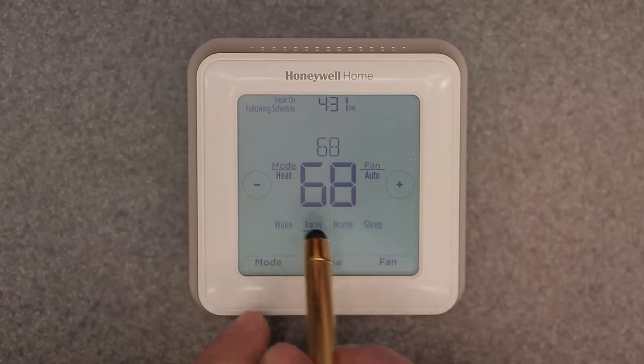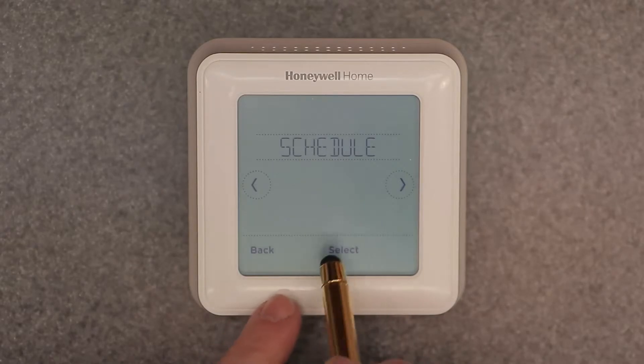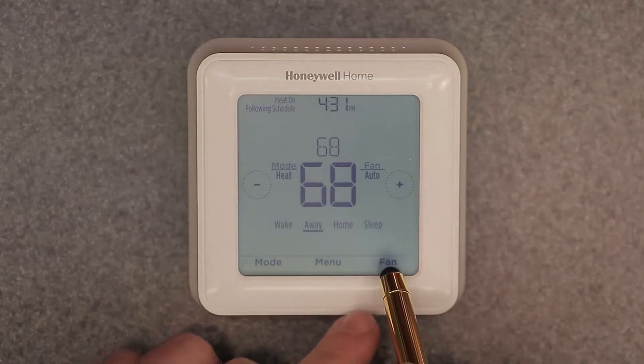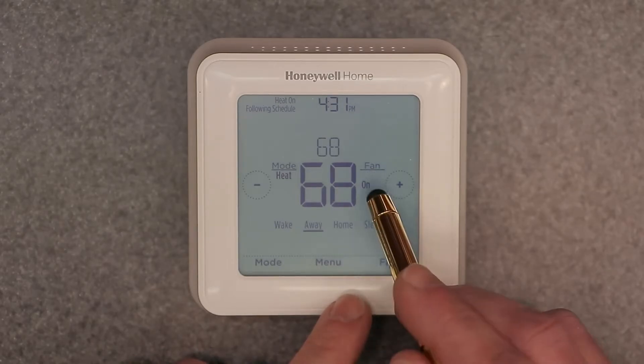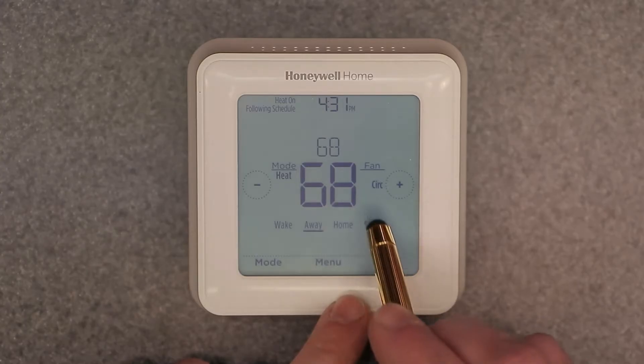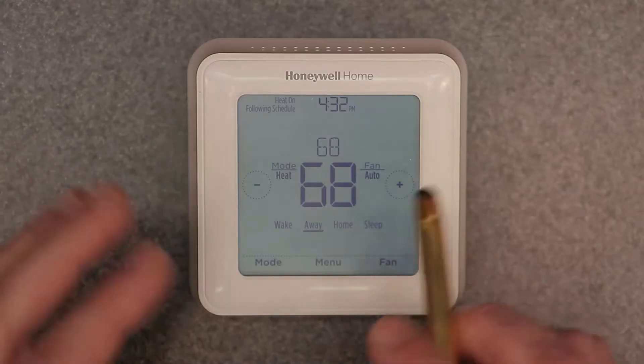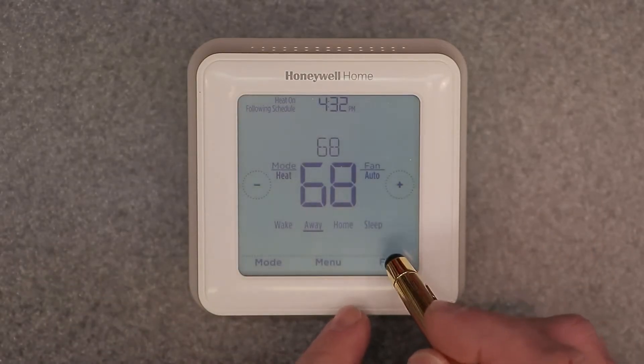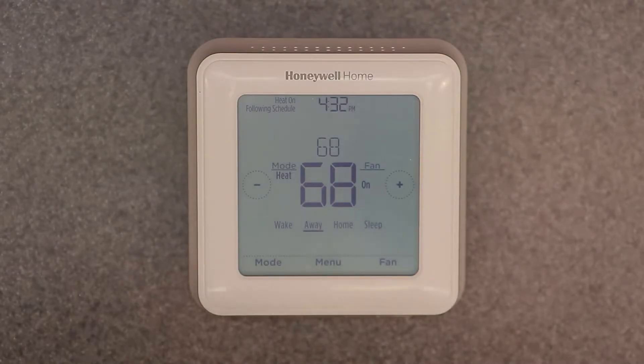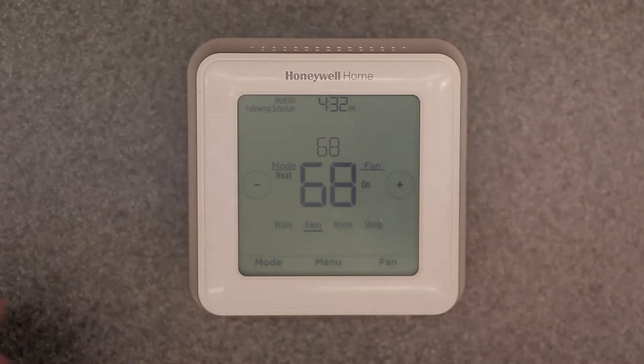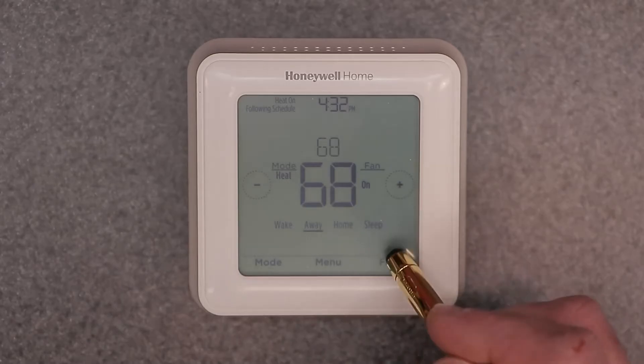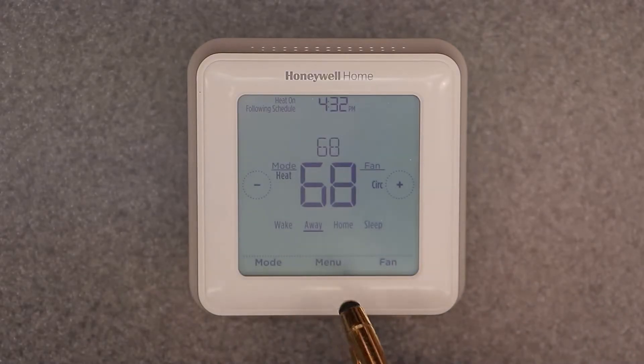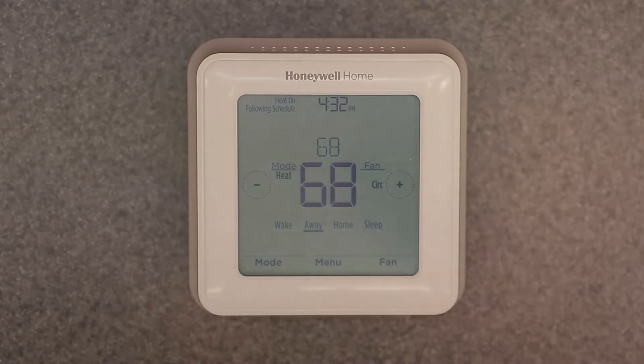Let's leave mode on heat for now. The menu button takes you through the menu — we'll come back to that. Fan has three options: auto, on, and circulate. Auto is what you want when running heating and cooling — it automatically turns the fan on. The 'on' setting keeps the fan constantly running regardless of the heating or cooling cycle, useful for circulating air through the house. Circulate, according to the manual, runs the fan randomly about 33 percent of the time.